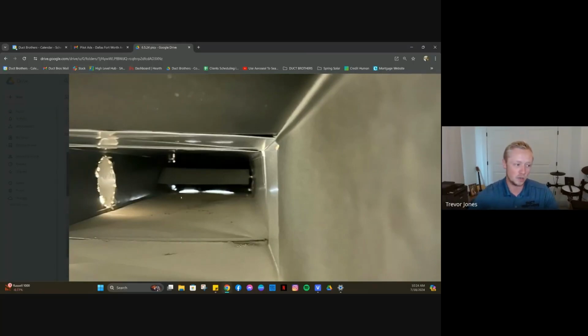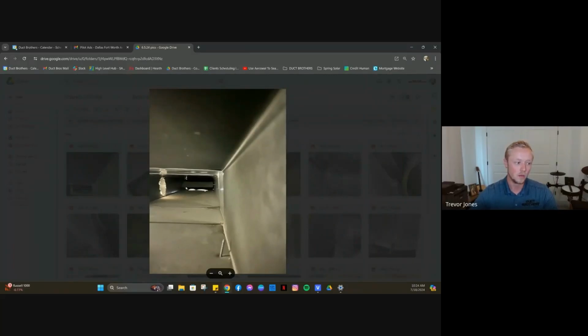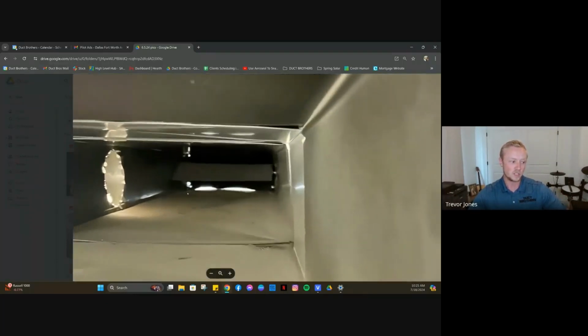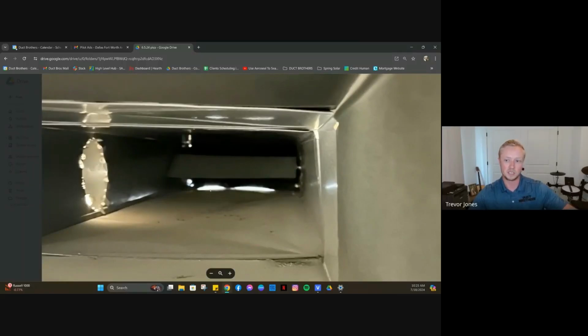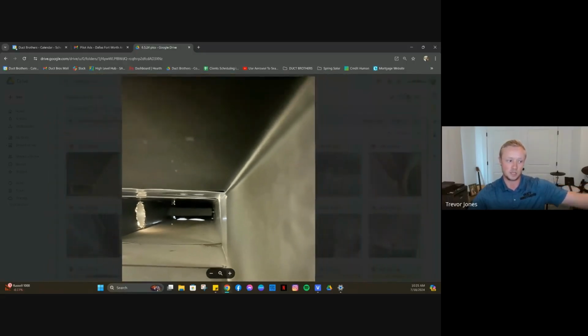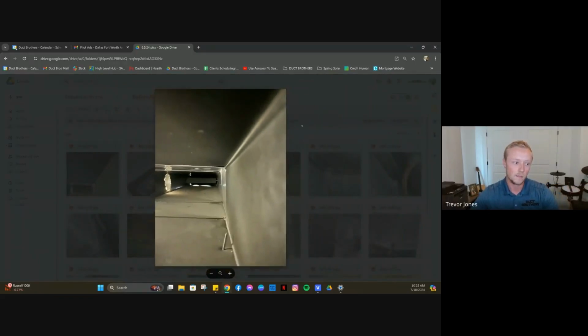The crazy thing is, you're thinking, okay, how would air quality be compromised if air is blowing through this? It would be blowing out of those holes, right? Well, what happens when your air shuts off is that it finishes pushing the air out and creates almost like a small amount of negative pressure in the vent. So all of a sudden, air's been blowing out of these holes, but once it stops, it's going to suck air in a little bit. It's going to pull that in and settle in here. And then as soon as it kicks on again, that's the first layer of stuff that blows out into the house — whatever nasty crap was sitting right near that got sucked into it. So that's kind of answering the air quality problem.